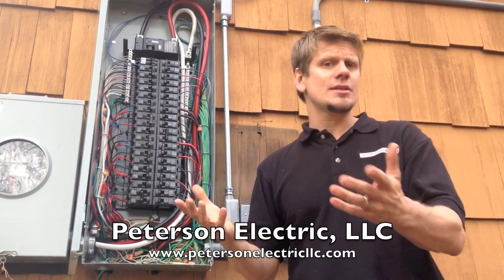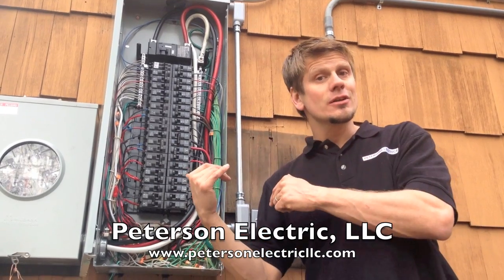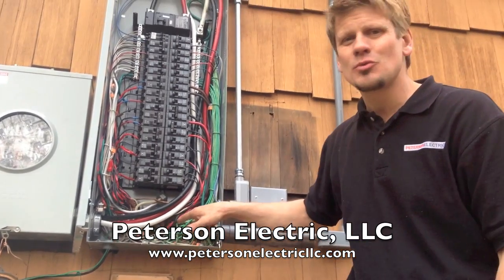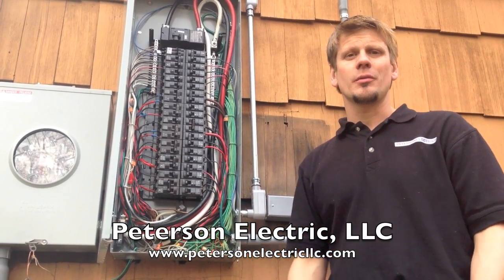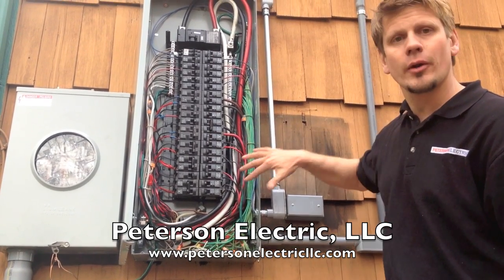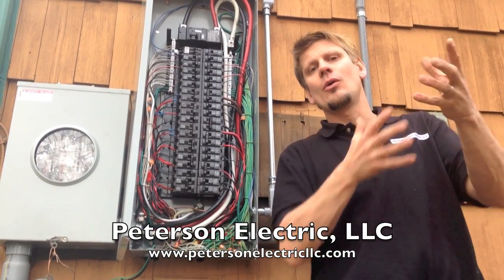Other than maybe we come out with testing equipment and find a way to set a subpanel with some new breakers, and we could tell you up front which circuits are going to set and which ones won't. Sometimes it's a little impossible, as you can see how all this bundles in — sometimes we can't figure out what neutral and what hot goes where. So it's going to be an open-ended part of the bid where we can't really tell you what we're going to set or not. Because once we set the breaker and put the neutrals to that breaker, then we'll know if it's setting. And if it doesn't, we have to go into the home and start tracing out that side of the house to figure out how it loops.